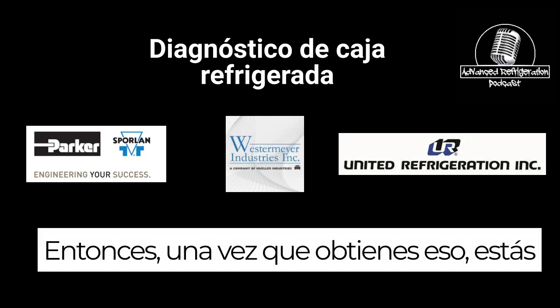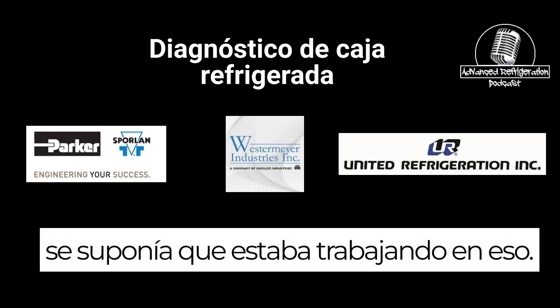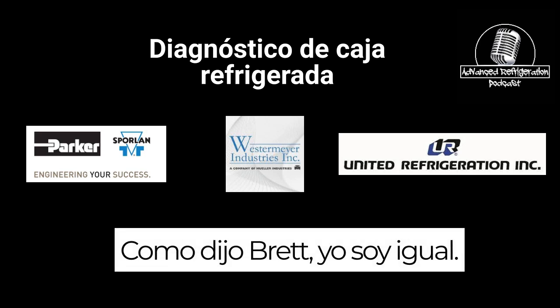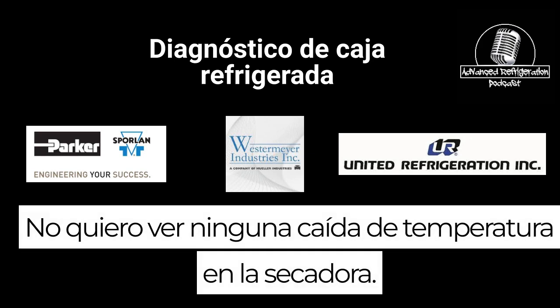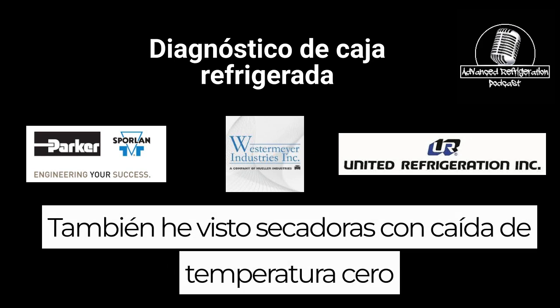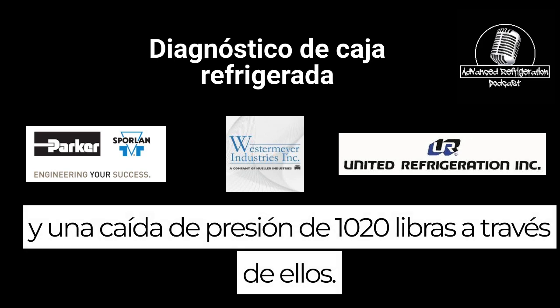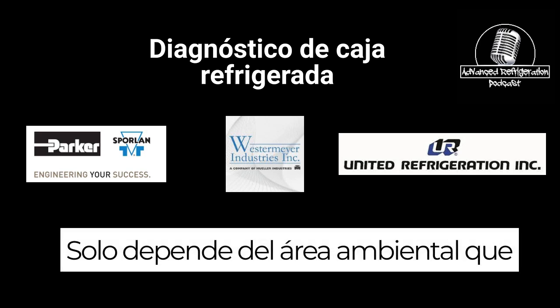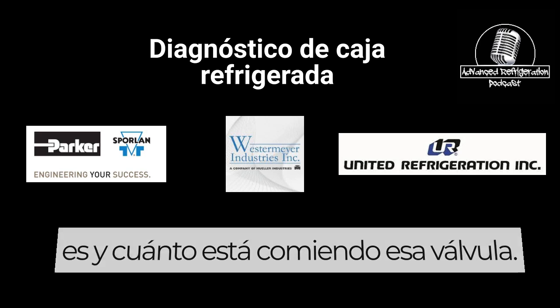So once you get that, you're supposed to be working on that. Yeah, like Brett said, I'm the same way. I don't want to see any temp drop across the dryer. I've also seen dryers with 0 temp drop and a 10, 20 pound pressure drop across. So it just depends on the ambient and the area that it's in.